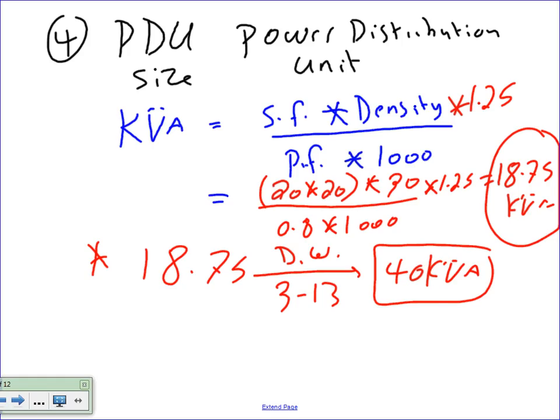The PDU and the UPS sizes, guys, could be completely different. But we need to standardize somehow on one size, so I gave you these numbers to play with, which is good enough. These are not industry sizes, but another manufacturer might have different sizes. Okay, so we got this one, piece of cake, right? Everybody gets that size, 40 kVA.